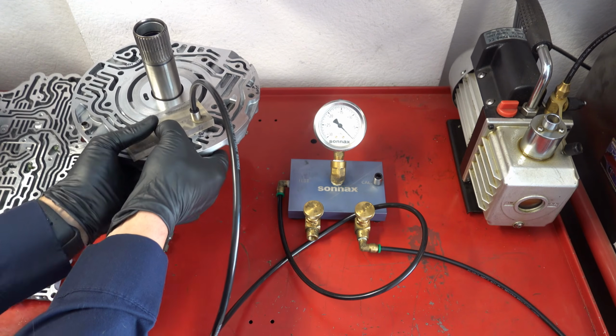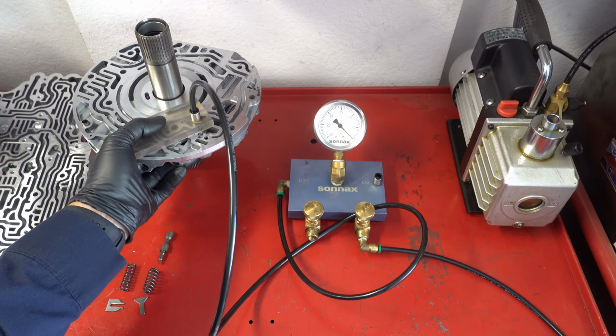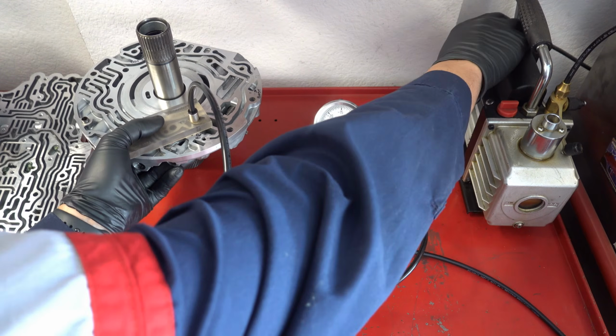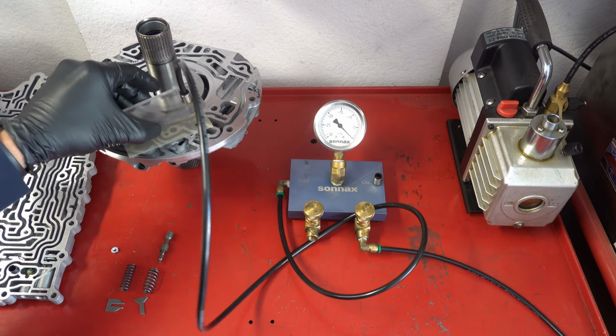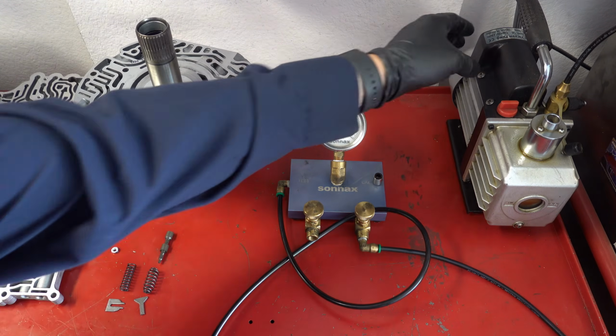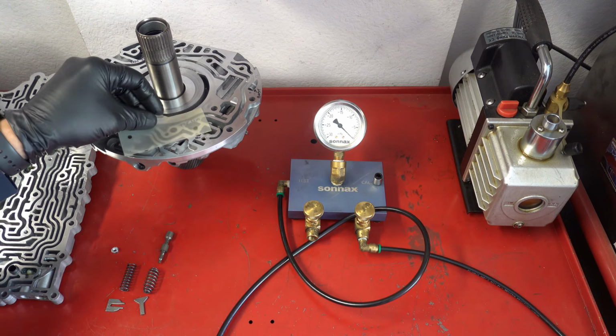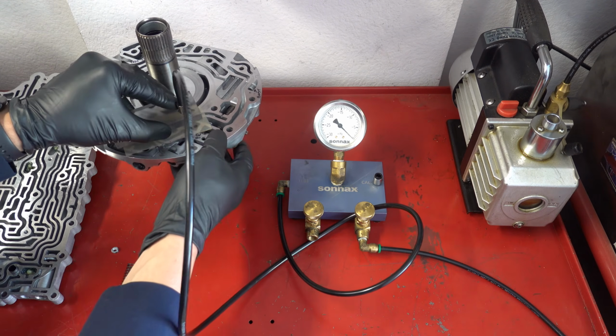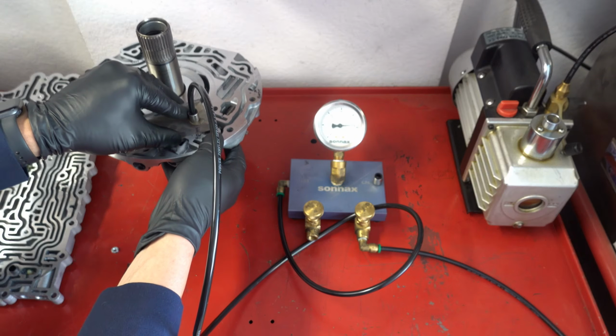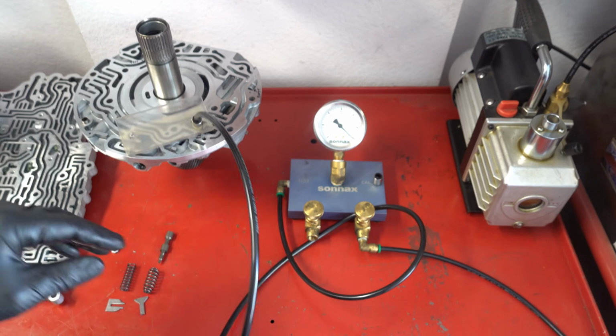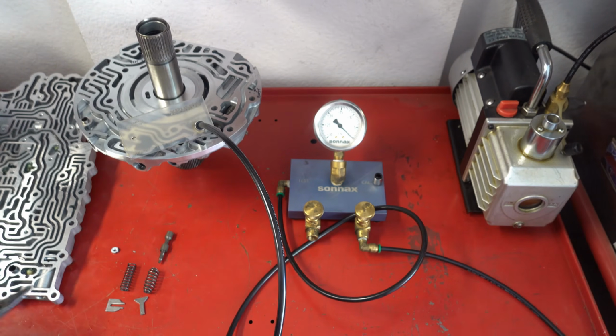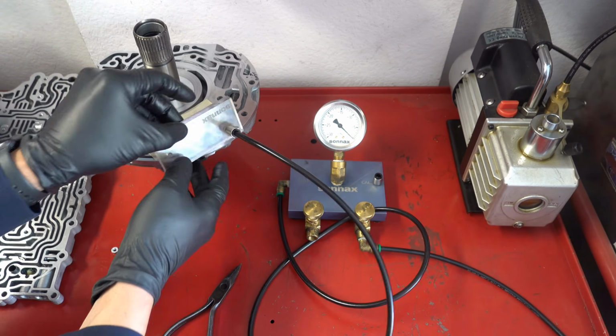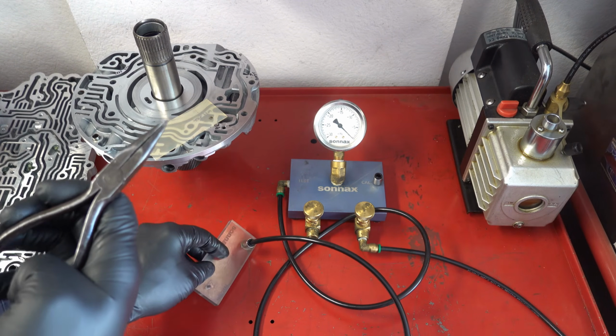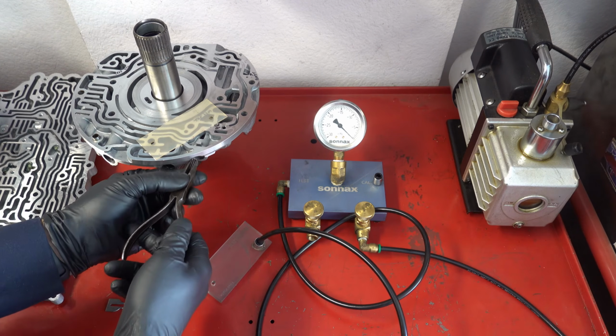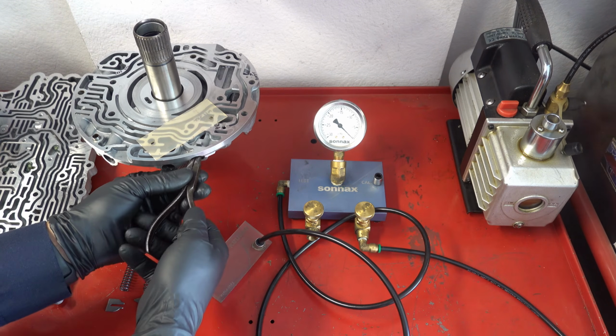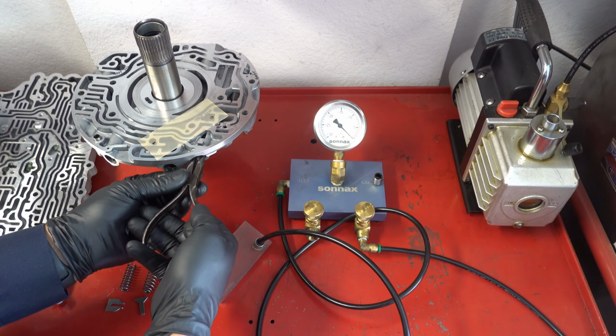Okay, make sure you're positioned. Apply a little bit of clamping force to it. You don't need to get crazy, but because I'm thinking my arm might be in the way, I'm going to turn it on first. And now we'll go ahead and set it up. Okay, you see that? It had a reading, and then it went right to 0. So we need to have our needle nose pliers handy, and we're going to pull out and hold the valve in place so that we can test it.